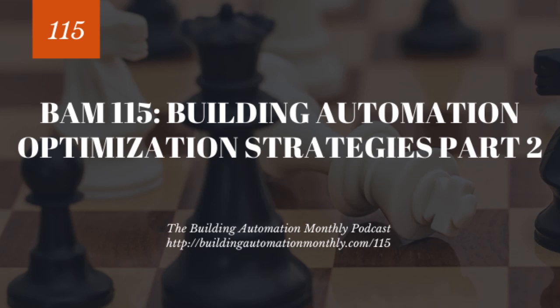Does that make sense? Is that kind of clicking why you would want that? Because that 200 CFM box is going to close down, the pressure is going to build up, and that DP sensor is going to start to cause the fan to ramp back. You could have starving boxes at those 1,000 CFM boxes.